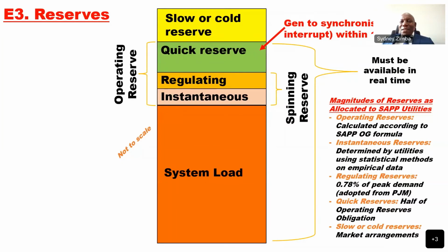So our requirement is that every generator with a capacity of 5 MVA should have an operational governor. That's the one which provides instantaneous reserve. A sudden change, the governor will operate, bring in more mechanical power to balance now that shortfall. It's localized. I always get questions saying, who controls frequency in your interconnected power system? And the answer people give is that it's ESCOM, because they've got the biggest generators. But for us as the coordinator, we say everyone participates.